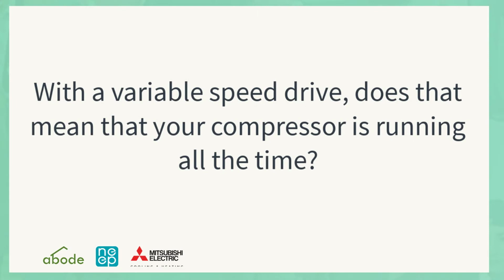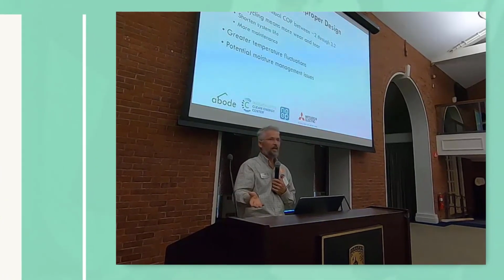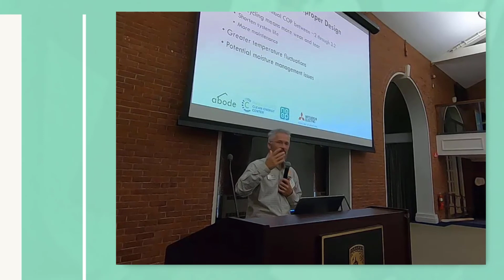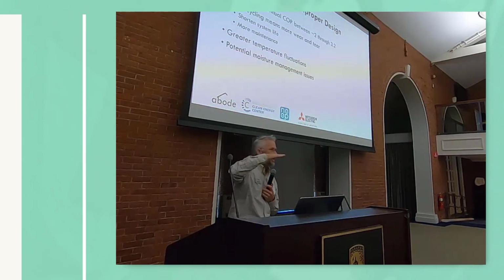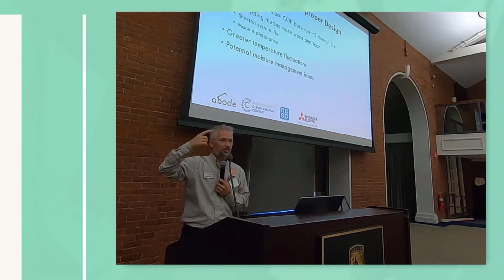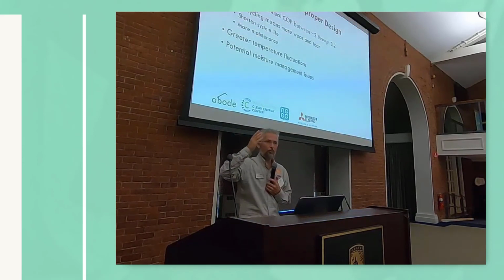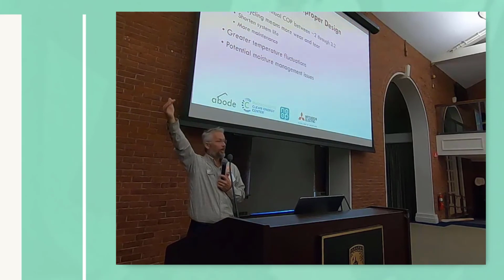Ideally, it's running all the time. Ideally, you're just sitting there and you're idle. The ideal circumstance is that, when the beginning of heating season starts, when it's 60 degrees or below outside, 55 degrees, and you need a little bit of heat just to keep the place warm, you're idling along at the lowest level that the heat pump can do, continuing to operate at 20% or 25% of its operating capacity. And then when you get to the peak of the season, it's running at 100%.